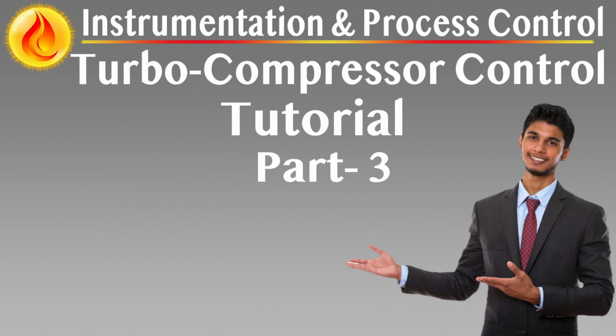Anti-surge to performance isolation. Anti-surge valves and performance controllers often act on the same process but have distinct goals. Decoupling ensures anti-surge logic retains control authority near the surge line. Performance logic does not inadvertently push the machine toward unsafe operation.